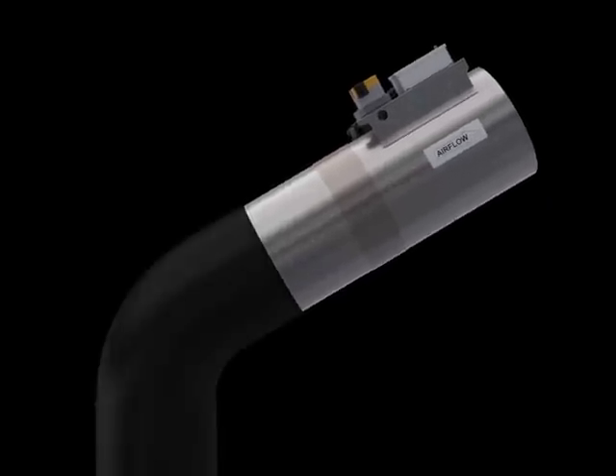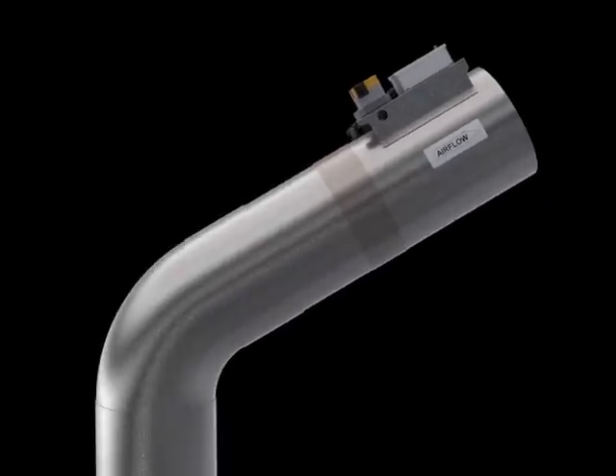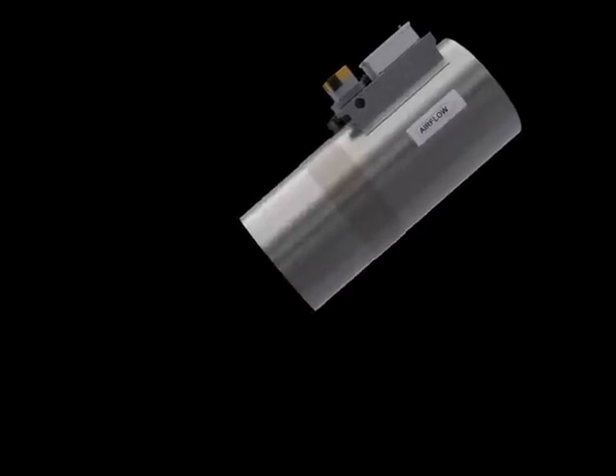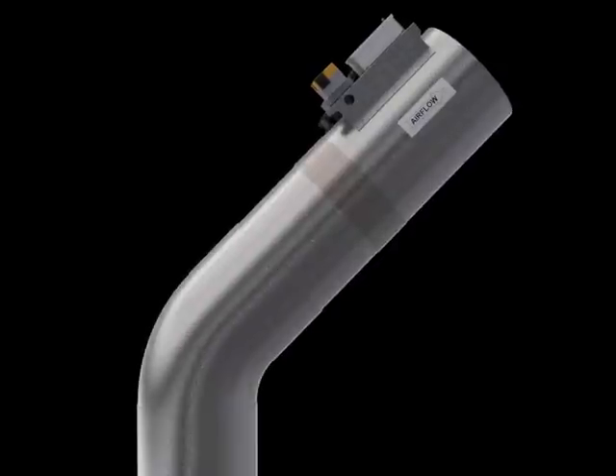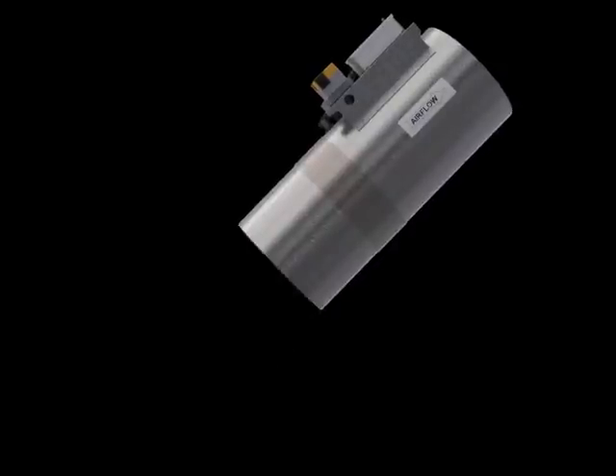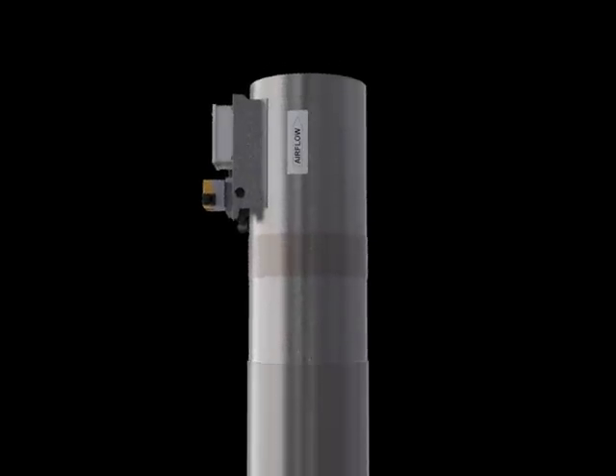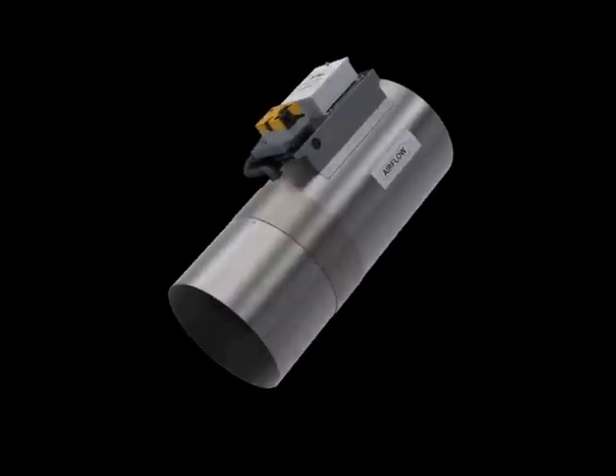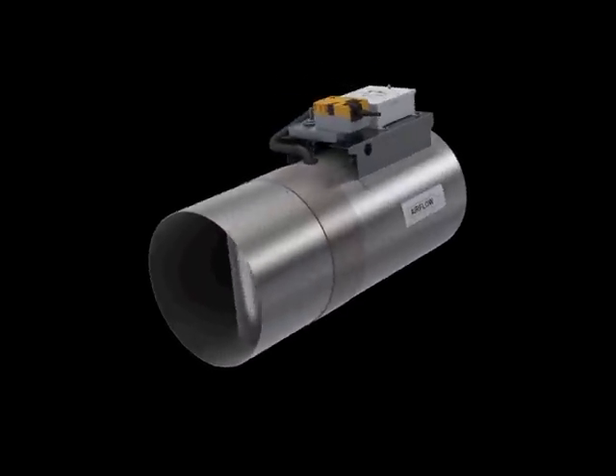Older valve designs such as Venturi must be ordered from the factory to be installed in either a vertical or horizontal plane, as they're factory calibrated for mechanical position of an internal spring cone arrangement. The AccuValve design alleviates any concern for the engineer, owner or contractor for accurate airflow control when installation parameters are challenged or changed.